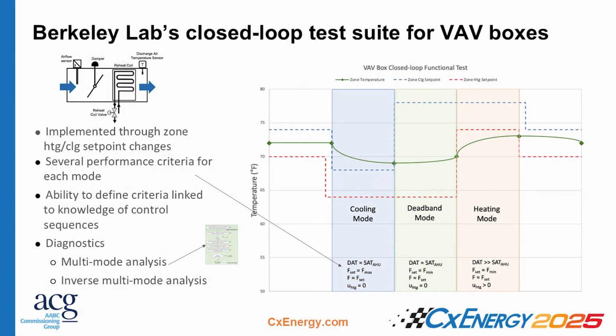So this is the example of our closed loop test suite for VAV boxes. This is looking at targeting the set points as opposed to individual components. So in this case, you're seeing the room set points driven very low to trigger a cooling mode response from the VAV box. And you have a series of functional tests that you're running through that and pass-fail criteria for that specific mode. Once you run that and you pass and fail those specific determinations, you go to the next mode, which is deadband mode, which is driving the set points very wide, so wide that the system couldn't possibly get to that temperature, right? And then you monitor the system during that period for a given amount of time.